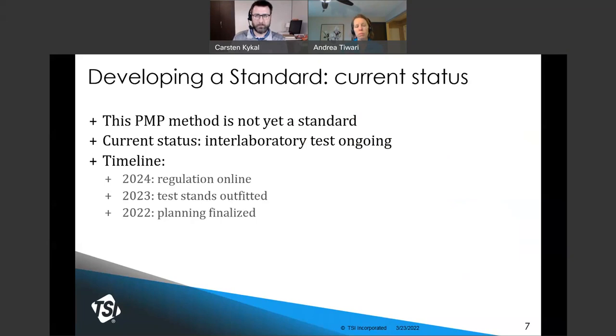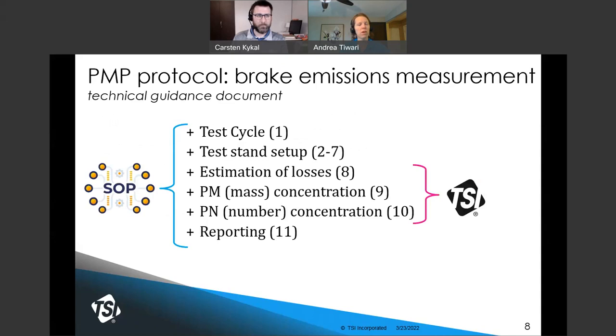Working backward from that time, test stands need to be outfitted during 2023, which means that 2022 is a key time for planning. The first section of the protocol defines the test cycle. Sections 2 through 7 describe how the system should be structured and operated. Section 8 covers characterizing losses within the test stand. Once those loss estimates are completed, you're ready to move into measurements of particle mass (PM) and particle number (PN), covered in sections 9 and 10. TSI has instrumentation relevant to sections 8 through 10. Section 11 specifies the information that must be included in the final report.